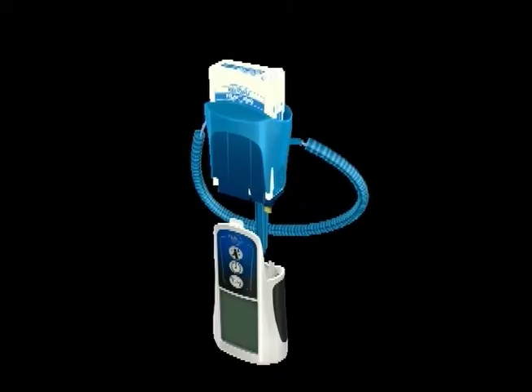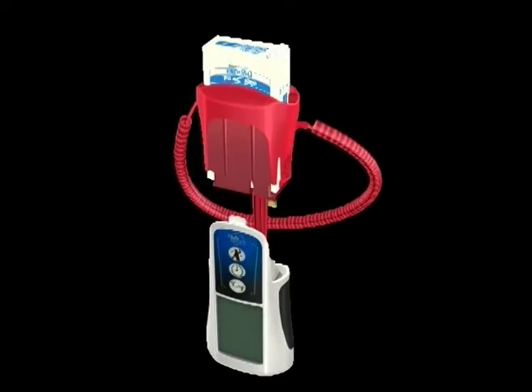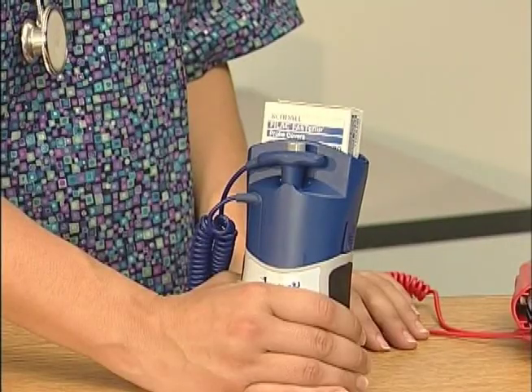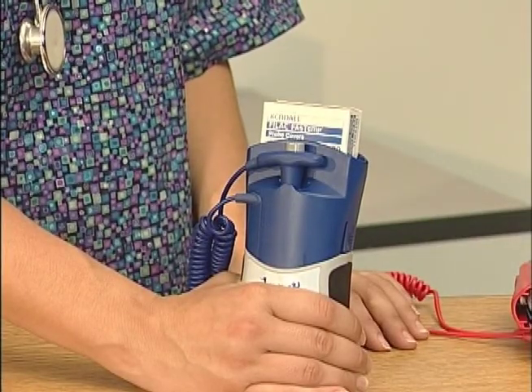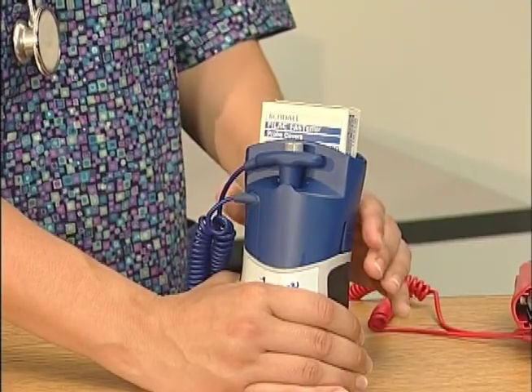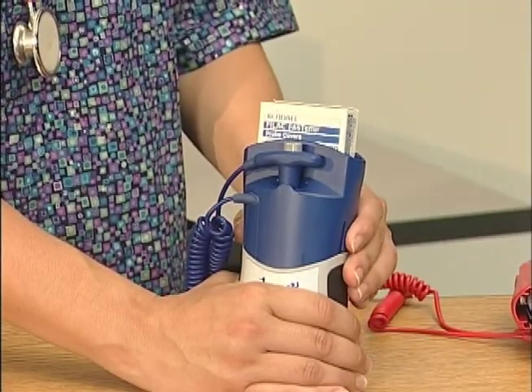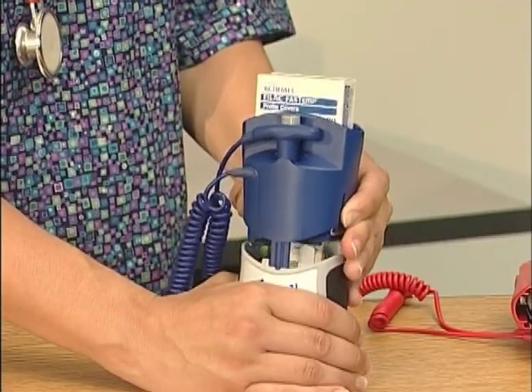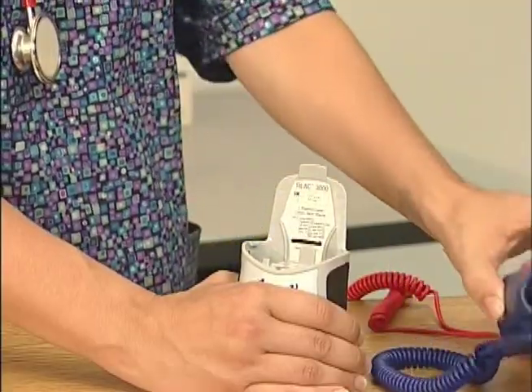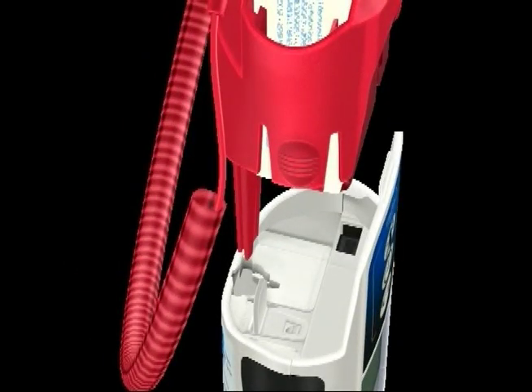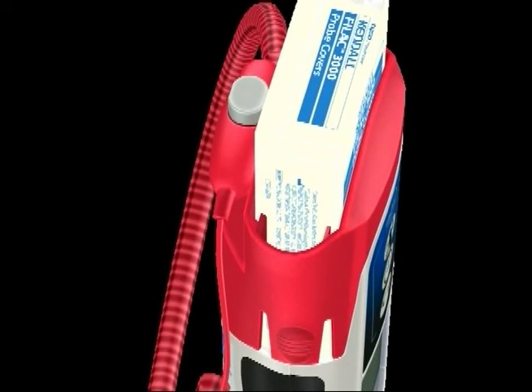The blue chamber and probe is used for oral and axillary temperatures, while the red chamber is used for rectal temperatures only. To remove an isolation chamber and probe assembly, grasp the isolation chamber from each side, squeeze inward, releasing the snaps, and slide the isolation chamber up to remove. To install an isolation chamber, align the probe well finger with the opening in the top of the unit, and slide the isolation chamber down until the side snaps click into place. The probe is connected to the thermometer automatically.